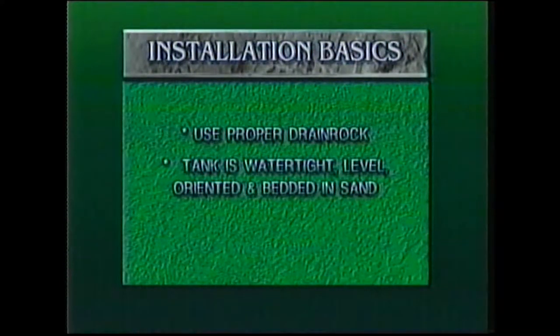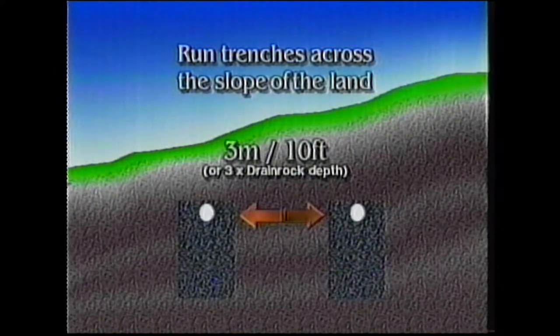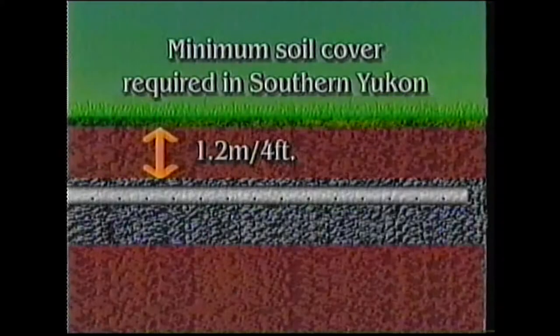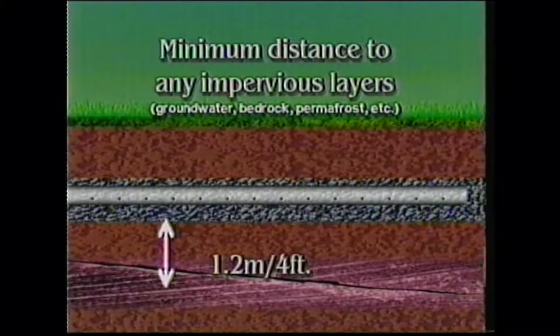Ensure your tank is watertight, level, oriented properly, and bedded in sand. Trenches must be dug across the slope of the land, and the distance between the trenches not less than three meters or ten feet, or three times the drain rock depth, whichever is greater. The amount of soil cover needed can vary depending on your location. Typical soil cover required in the southern Yukon is 1.2 meters or four feet without insulation. In some instances, this can be reduced by using five centimeters or two inches of rigid styrofoam to insulate the system before backfilling.